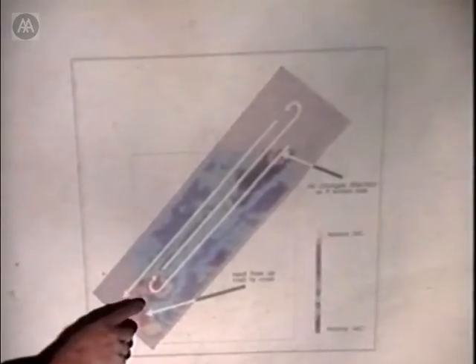So it blows into one core, goes along that core to the corner, and then at the corner it goes across to the next core, back again, across to the next core, and back again. By the time it's done that, it arrives in the room almost at the same temperature as the air in the room should be, 21 degrees or thereabouts, and it's transferred all its heat to the concrete slab.